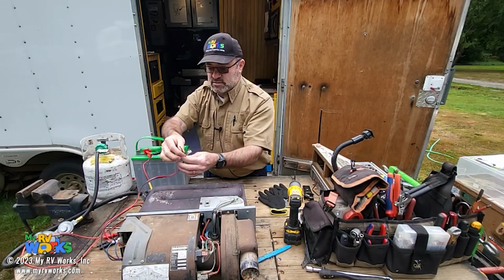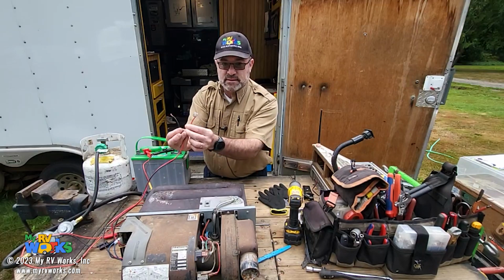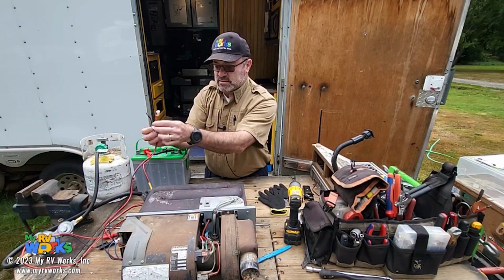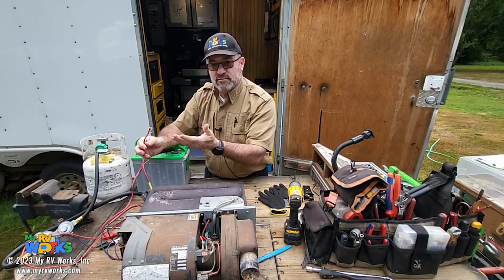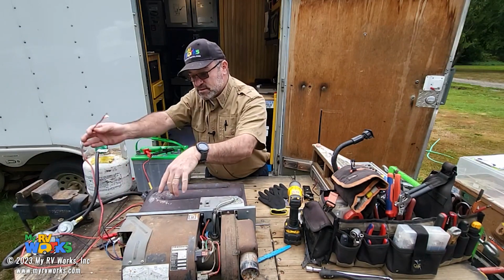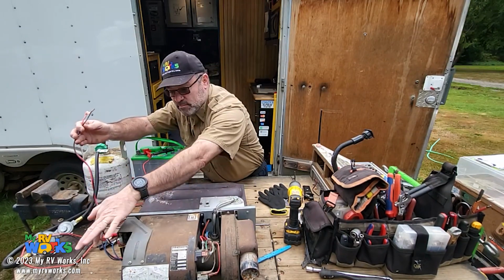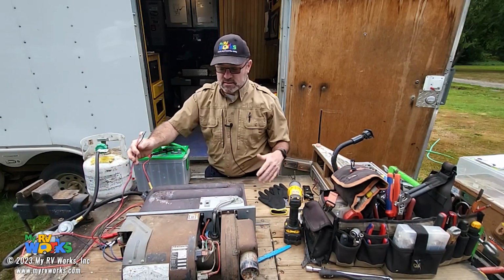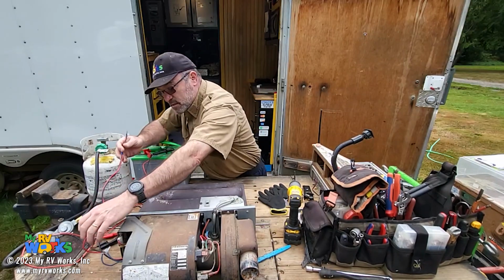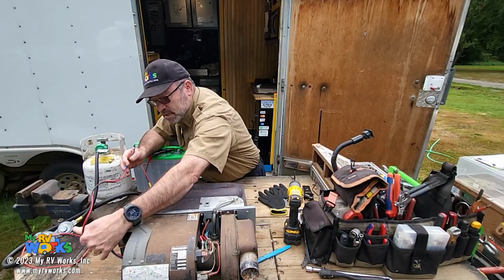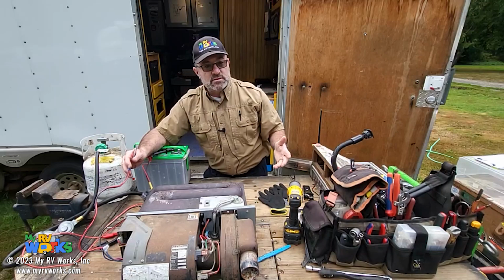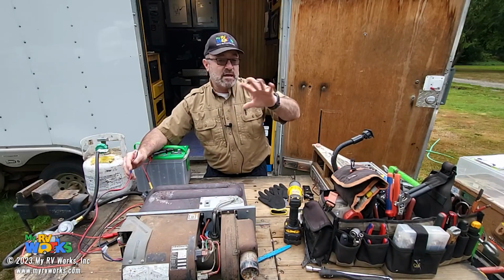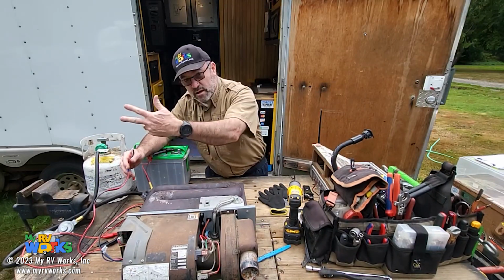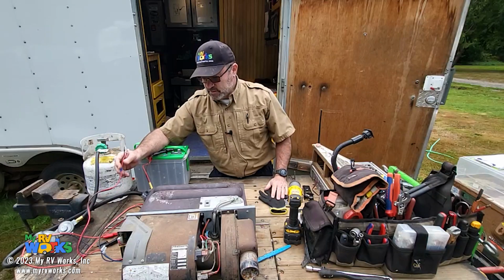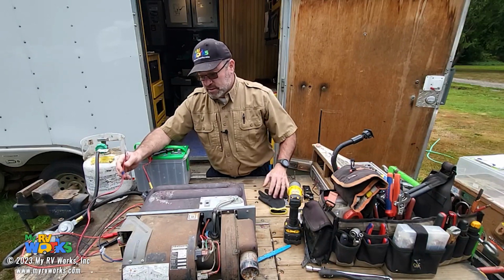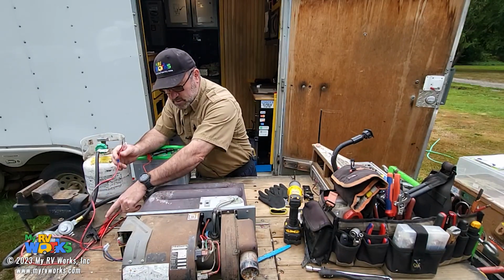When I connect these two wires, I am basically becoming the thermostat. These are wires that leave the furnace, and typically they're blue. In this instance they're two light blue wires. Sometimes they're blue with white stripes, sometimes dark blue, but they'll have some element of blue regardless of the manufacturer of your furnace.